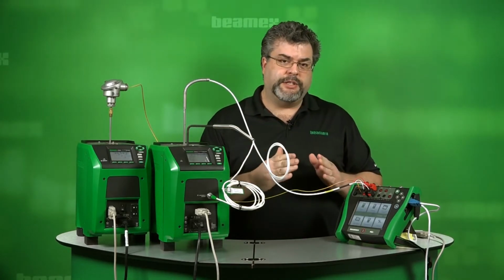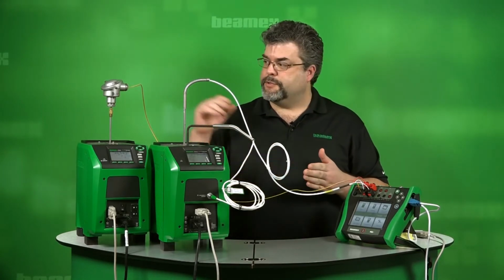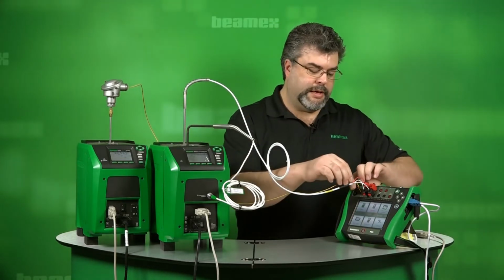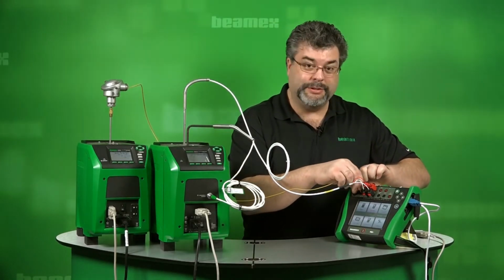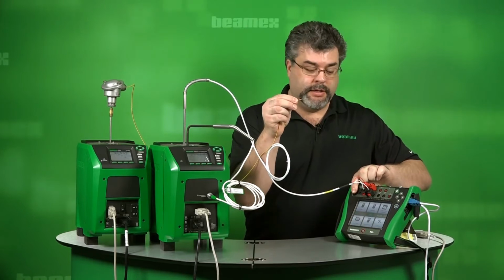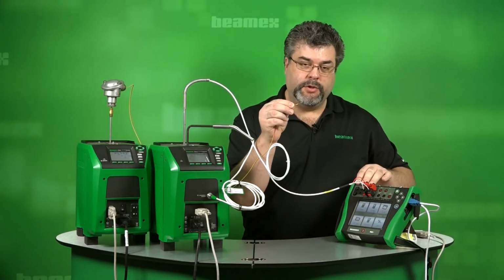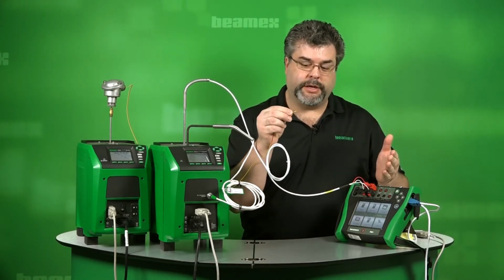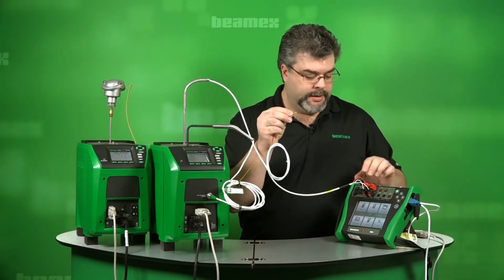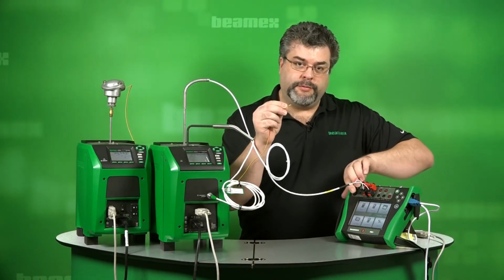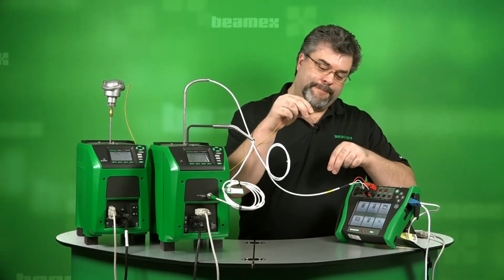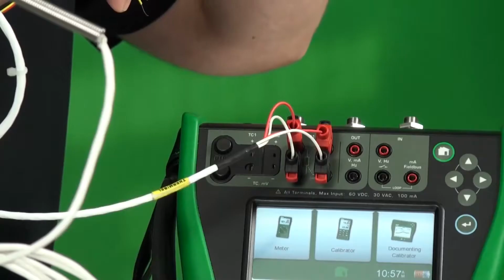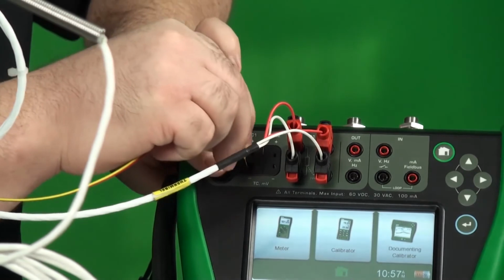Let's look at our connections for the temperature probes themselves. We have our thermocouple. In this case, I don't have a thermocouple plug, I have bare wire. On the calibrator, you can connect using a thermocouple plug, or you can use bare wire. If you use bare wire, we have 2 little buttons here. You simply press them down, insert the wire, and let go. And that makes your connection for you. So let me do that.